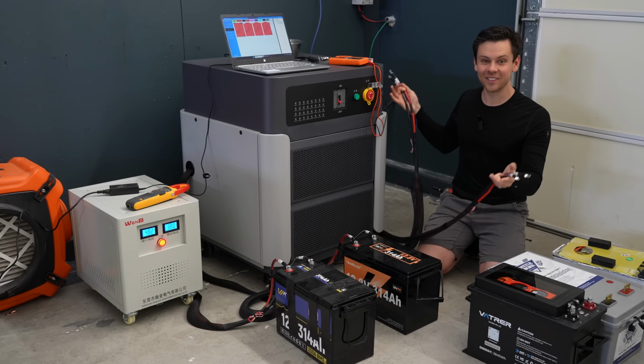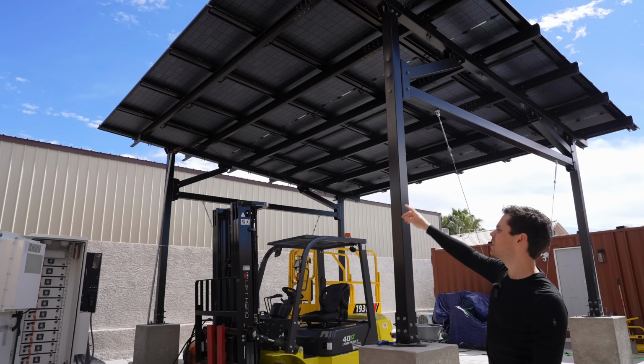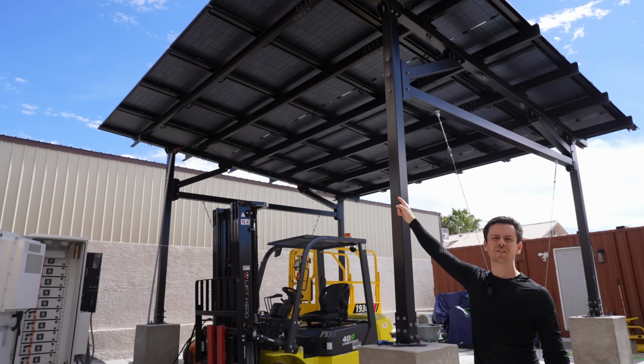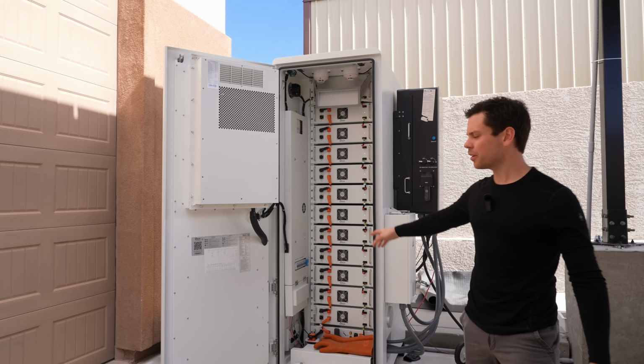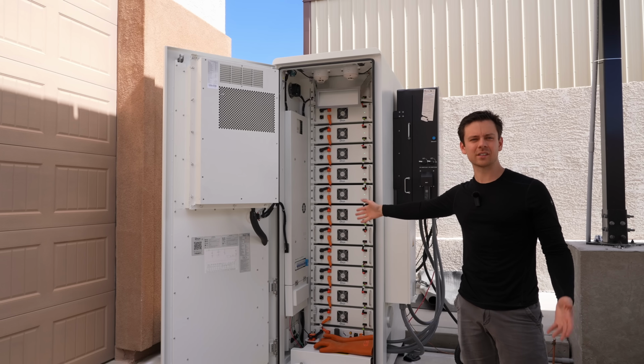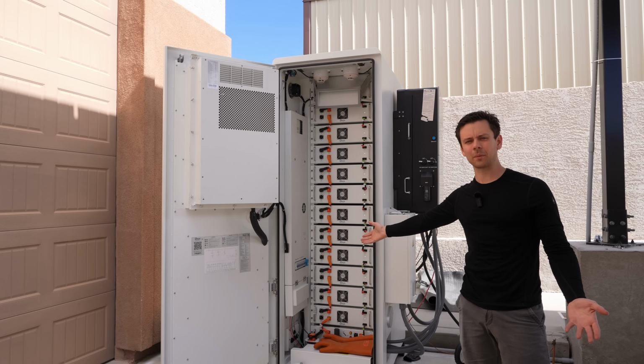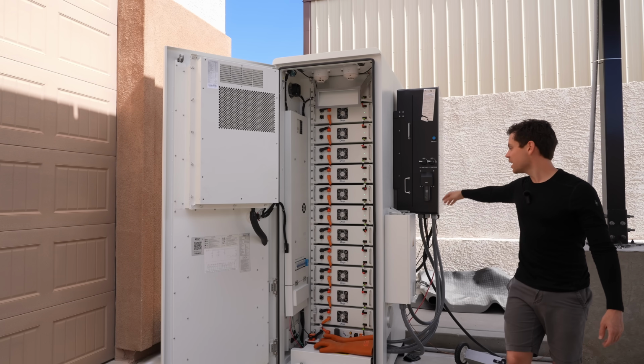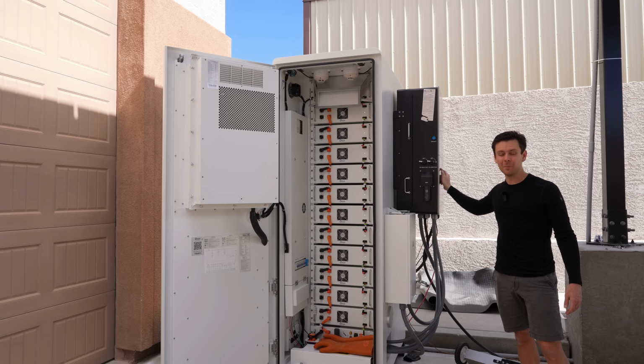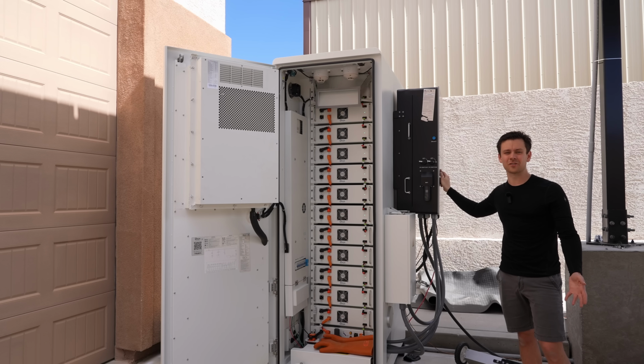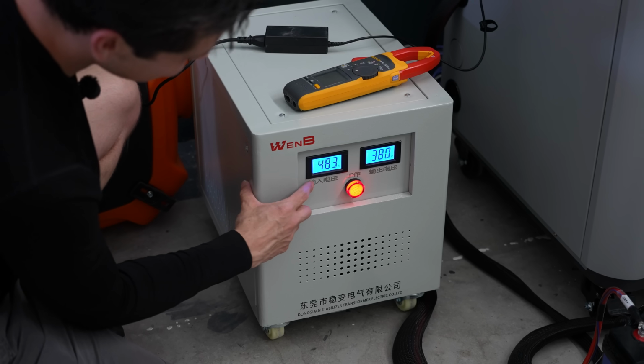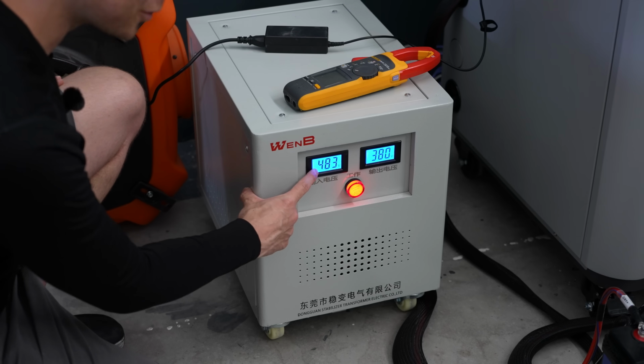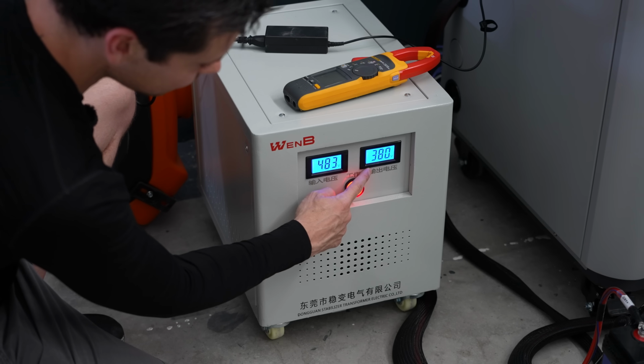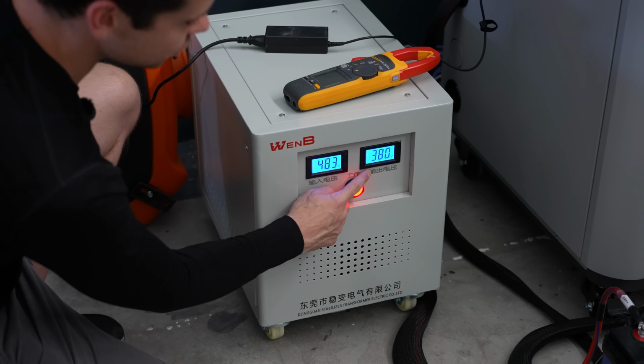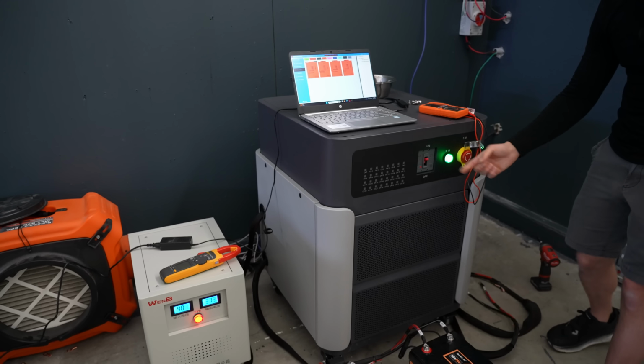This whole system is off-grid 3-phase. First I took a single series string from the solar carport and used all that solar to charge up these batteries. This is a high voltage 60 kilowatt hour battery, and it runs the Sol-Ark 60K, but that does industrial 480 volts. So I bought this small transformer that steps down the 480 volt 3-phase to 380 volt 3-phase, which is used in China. And now we have power.